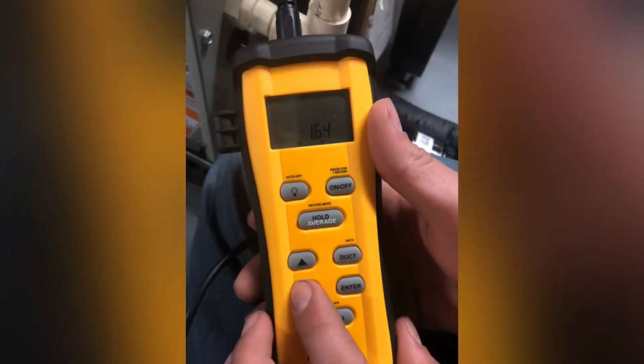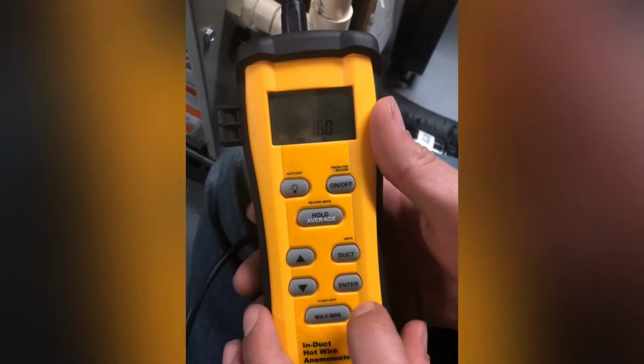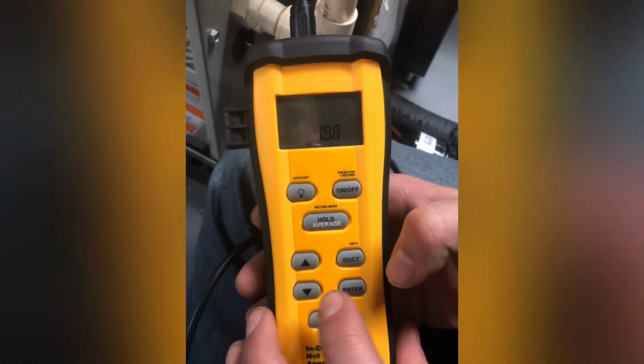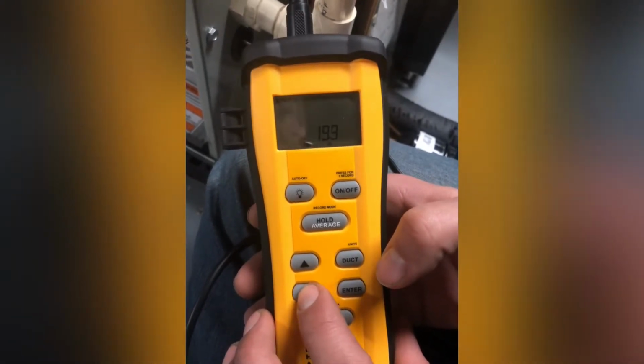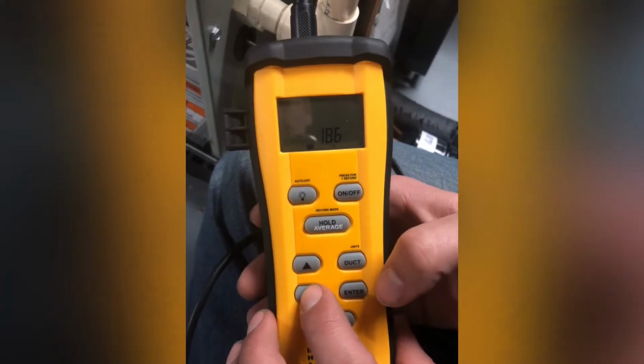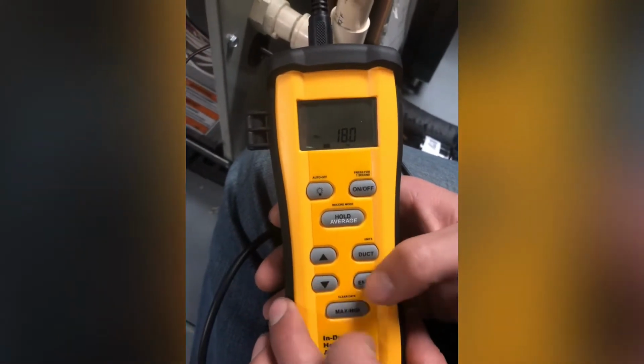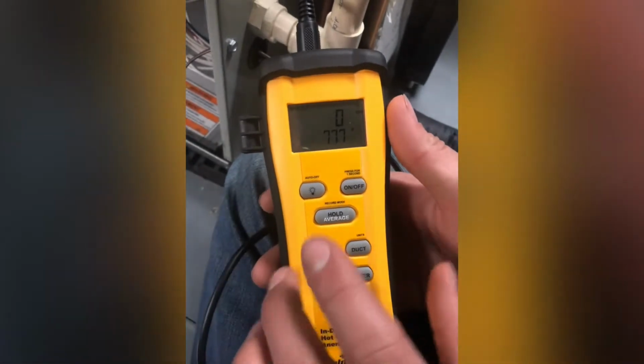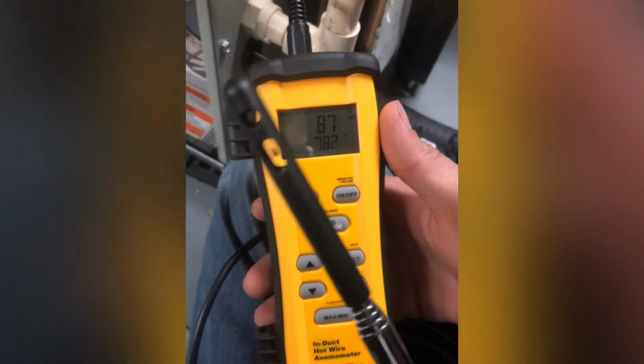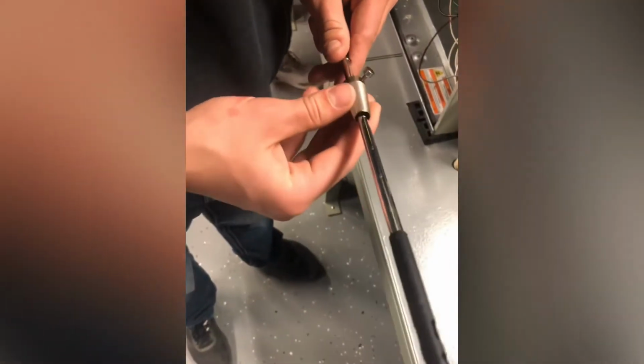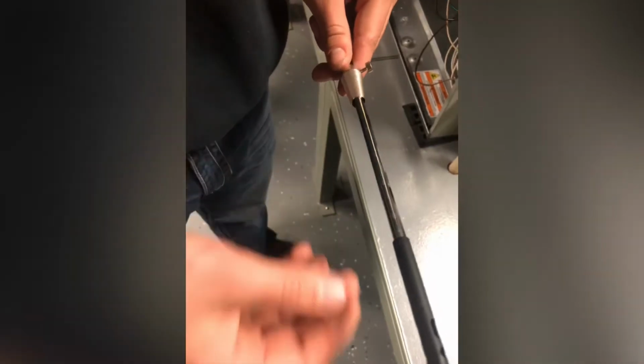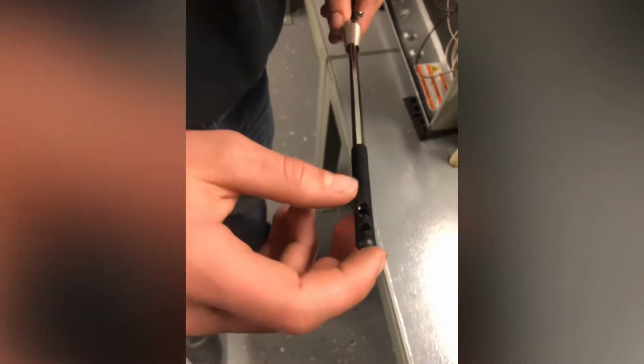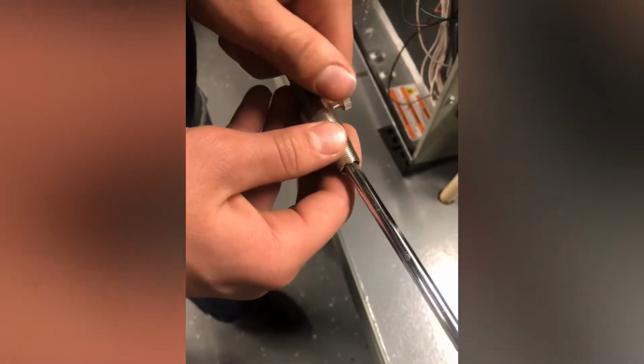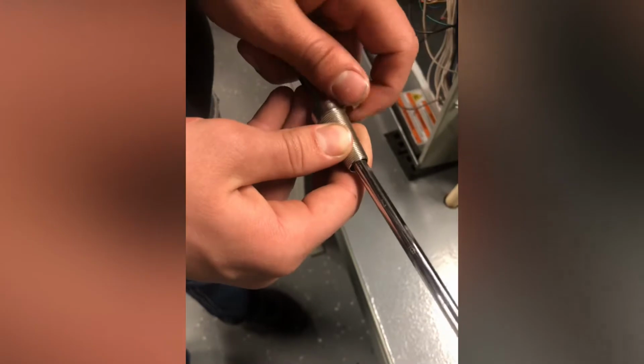Now it's going to ask us how big the duct is. Ours is 16 inches. So you put the dimensions in, and the height is 18. Alright, so now we have the duct size in there, and all that's left to do is stick our probe in. So now we're going to go attach the cone to hold it into the duct. And we're going to want the tip of the anemometer to be in the center of the duct. That's where we get the best, most accurate reading. So we're going to go down on the measurement line to 8 inches because our duct is 16 inches wide. We're going to tighten this down.